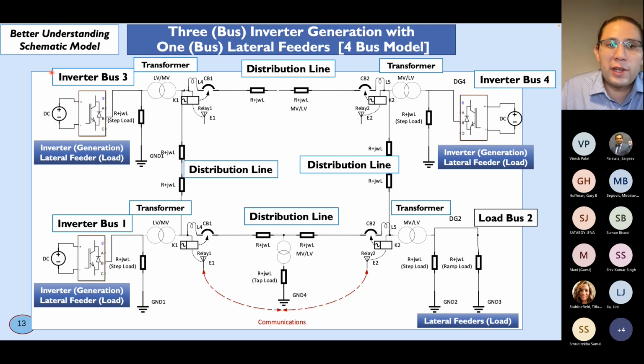So we have the inverter connection here where we convert the DC, which is a power DC source from the solar panel, through an inverter. And then we pass to the transformer. This is feeding its own load, like some lateral feeder within the DG3 in this case. And this connects to the distribution line, which, as we can see, is a short line, and which is now medium voltage, the way it is presented in this figure. And we have the different relays and the communication system here, as can be seen in the bottom figure as well. In the load side, we have different lateral feeders with different types of loads. Here I named them arbitrarily, like step load and ramp load, but there can be many types of loads, like I presented before.